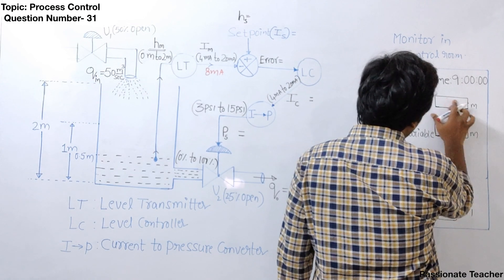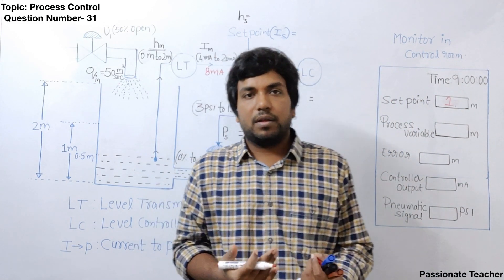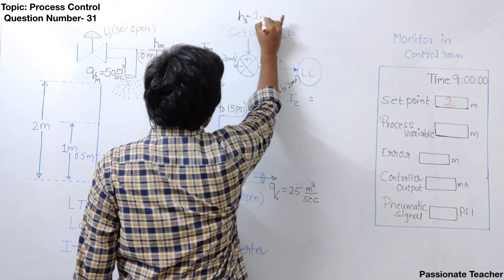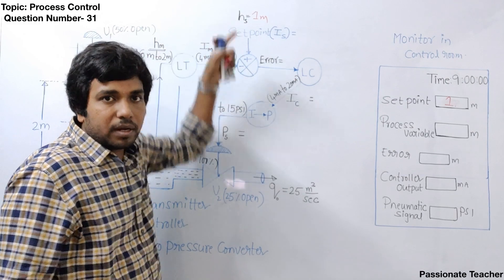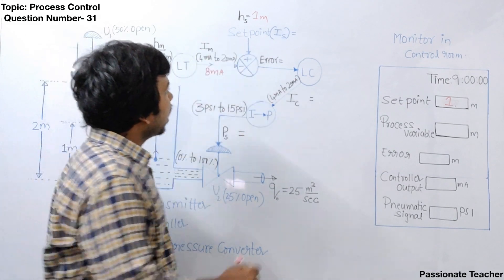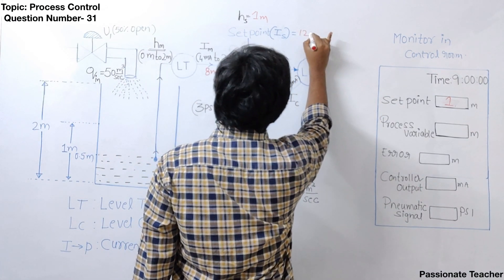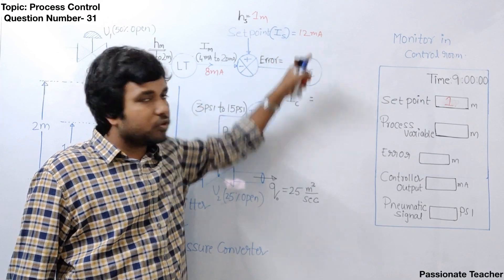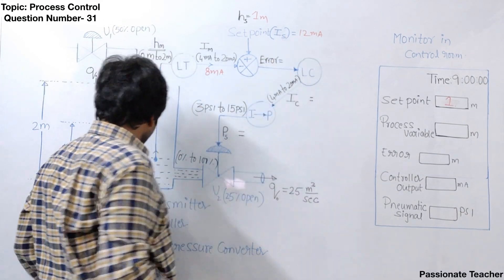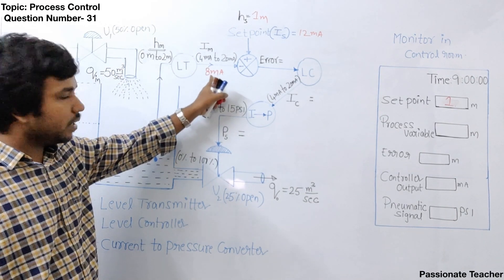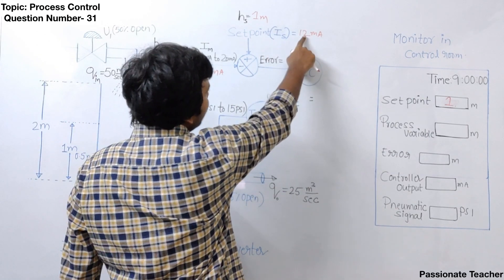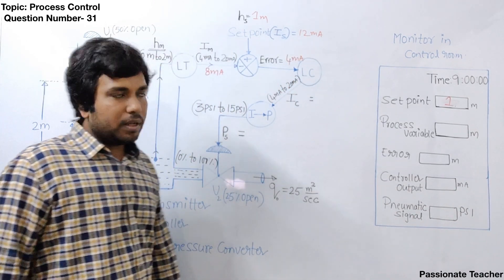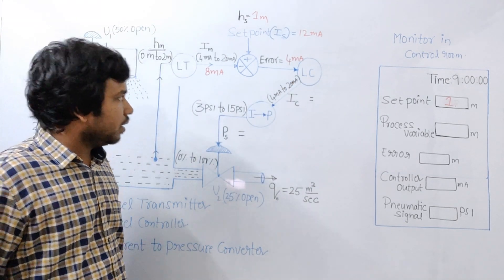If the engineer enters the setpoint as 1 meter, it means the engineer expects the water level to be at 1 meter. At the instrumentation level, this setpoint of 1 meter is automatically converted to a current signal of approximately 12 milliampere. Now we have 0.5 meters of water level calibrated as 8 mA, and the desired setpoint is 12 mA. So the error signal is 12 mA minus 8 mA, which equals 4 milliampere.